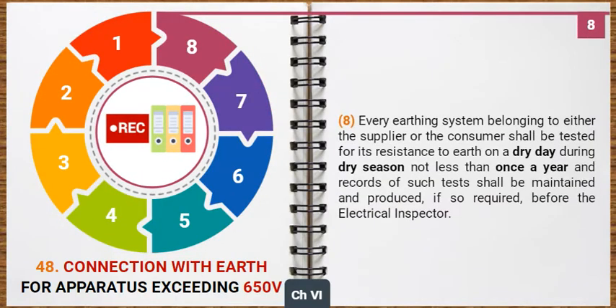Every earthing system belonging to either the supplier or the consumer shall be tested for its resistance to earth on a dry day during dry season not less than once a year, and records of such tests shall be maintained and produced, if so required, before the electrical inspector.